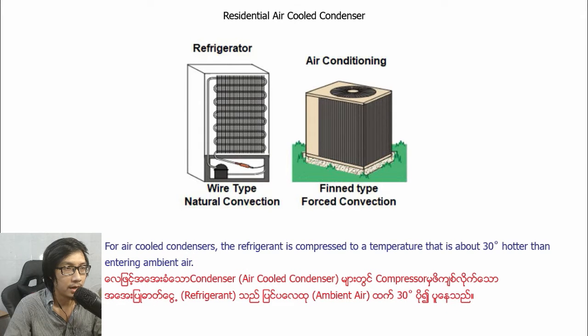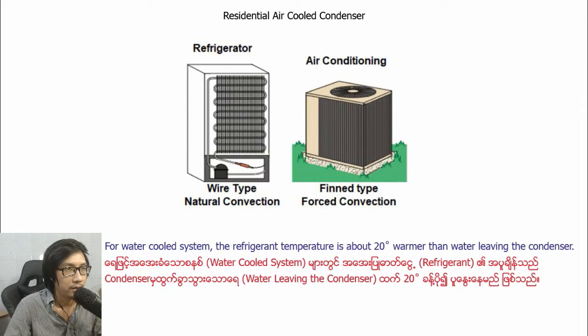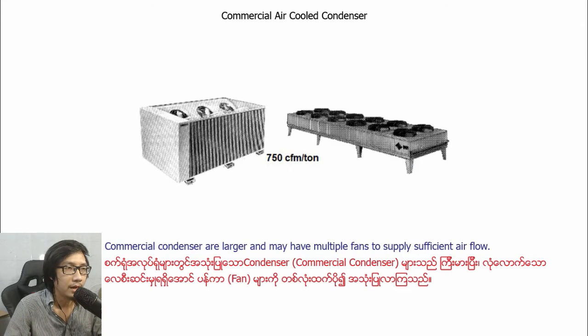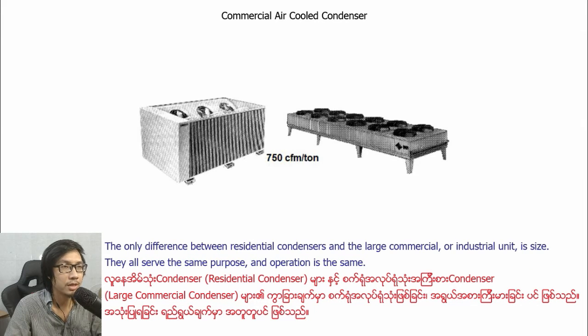For an air cooled condenser, the refrigerant is compressed to a temperature that is about 30 degrees hotter than the entering ambient air. For a water cooled system, the refrigerant temperature is about 20 degrees warmer than water leaving the condenser. Commercial air cooled condensers are larger and may have multiple fans to supply sufficient airflow. The only difference between a residential condenser and a large commercial or industrial unit is size. They all serve the same purpose and operation is the same.